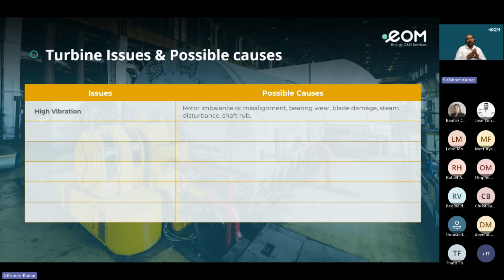And also bearing wear, as I said earlier. Bearing wear occurs because of not performing bearing inspections, minor bearing inspections, and not performing bearing tests like DP or ultrasonic tests. It also occurs because of lube oil contamination. Then between the rotor and the bearing there is no lube oil film formation, so that causes more heat and friction. That causes the bearing wear, eliminating the entire white metal on the bearing, and the bearings will be damaged and vibrations will occur. Sometimes there is the possibility of blade damage because of blade erosion and blade cracks, and also steam disturbances, and shaft rub, causing high vibrations.